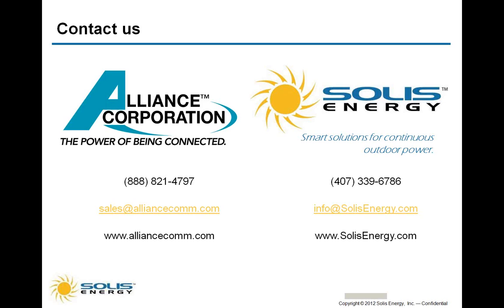Gel cell batteries will provide approximately 3,000 deep cycles, whereas an AGM will provide about 500 deep cycles, and by deep cycle we mean a 50% discharge. AGM batteries will retain more power in a very cold environment, such as minus 20C to minus 40C, and may be a better fit in those environments, but otherwise we recommend a gel battery. The batteries typically last 5 to 7 years because we size them properly. High heat environments or undersized systems will shorten battery life to closer to a 5-year time frame.